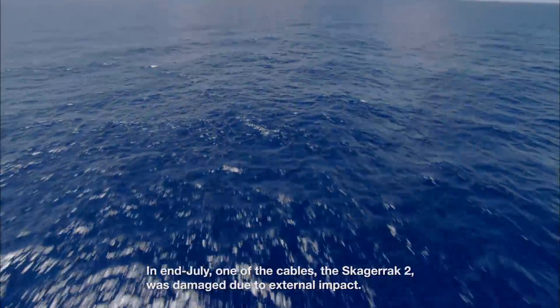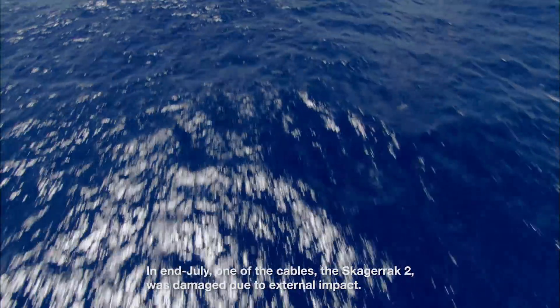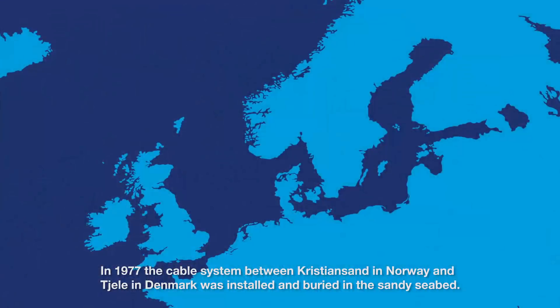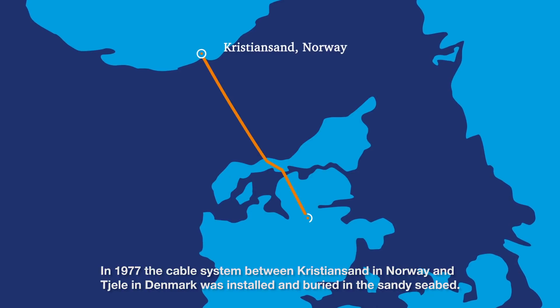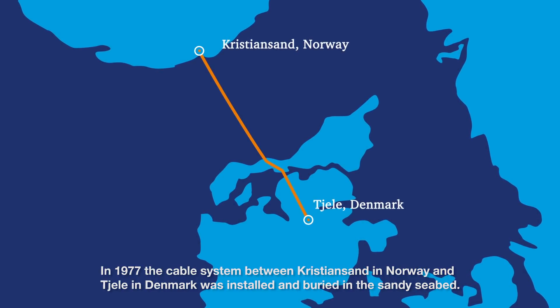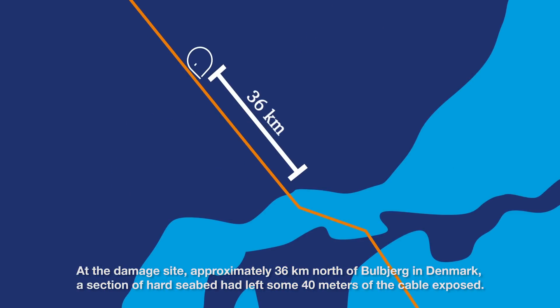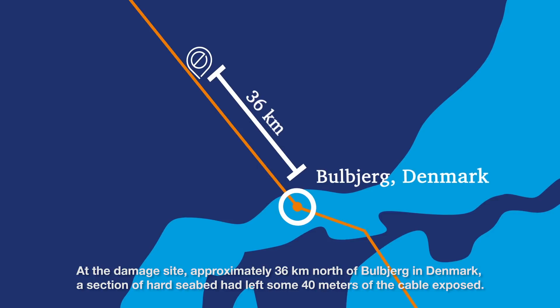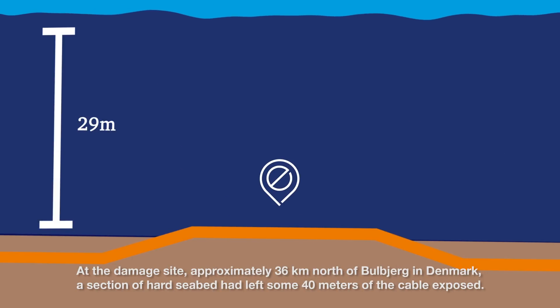In the end of July, one of the cables, the Skagerrak 2, was damaged due to external impact. In 1977, the cable system between Kristiansand in Norway and Tjele in Denmark was installed and buried in the sandy seabed. At the damage site, approximately 36 km north of Bulbjerg in Denmark, a section of hard seabed had left some 40 meters of the cable exposed.